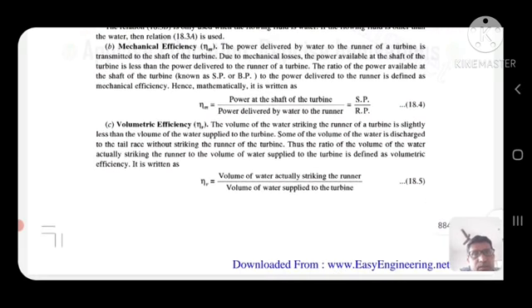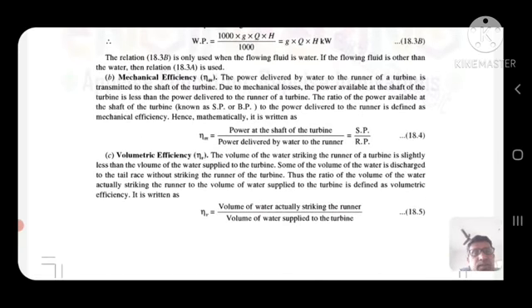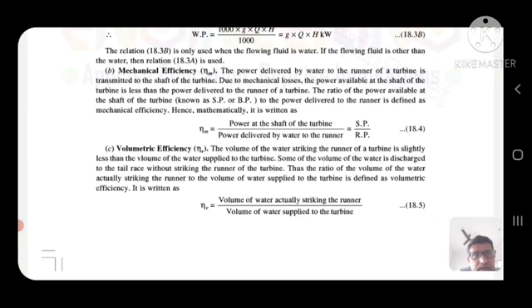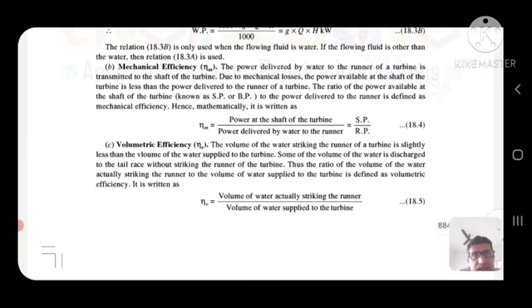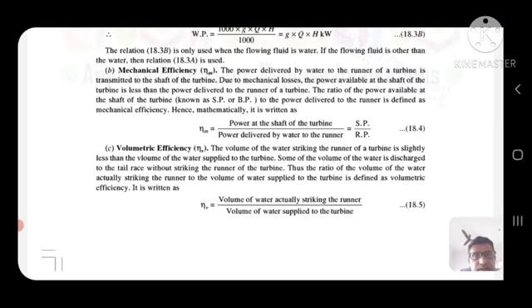Volumetric efficiency: the volume of water striking the runner of the turbine is slightly less than the volume of water supplied to the turbine, as some water is discharged to the tail race without striking the runner. Thus, volumetric efficiency η_V = volume of water actually striking the runner / volume of water supplied to the turbine.